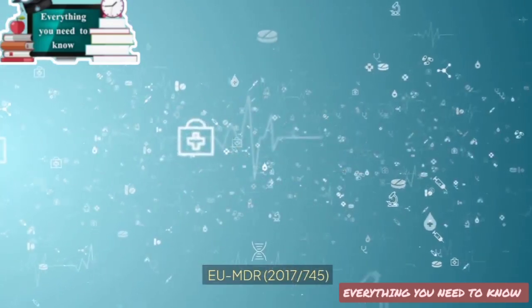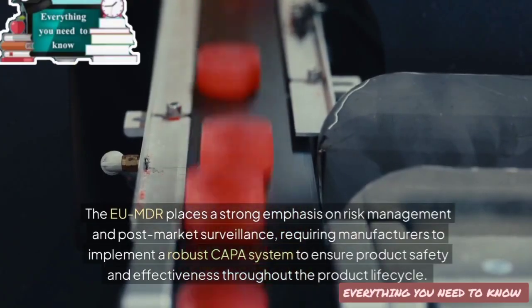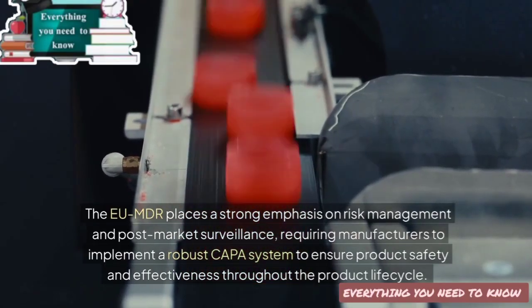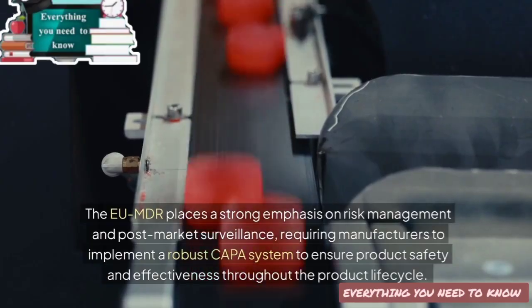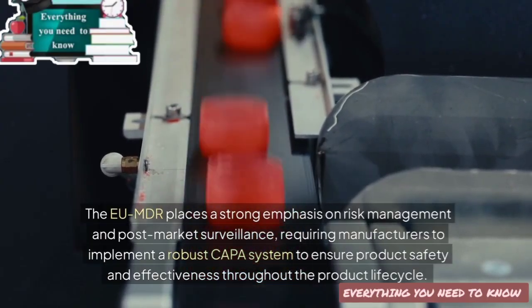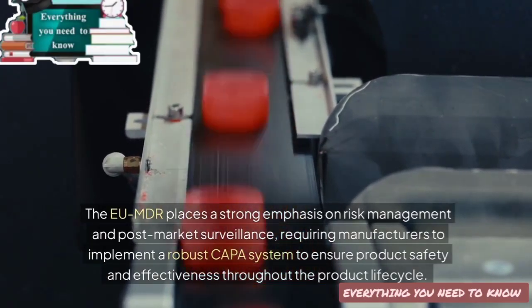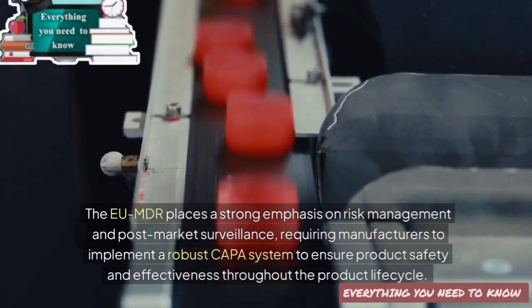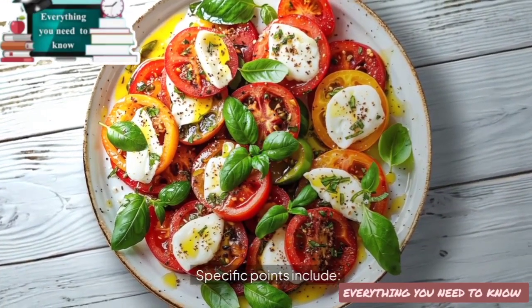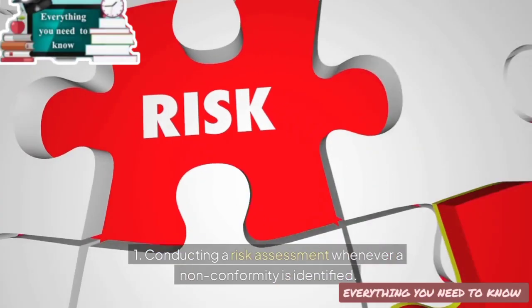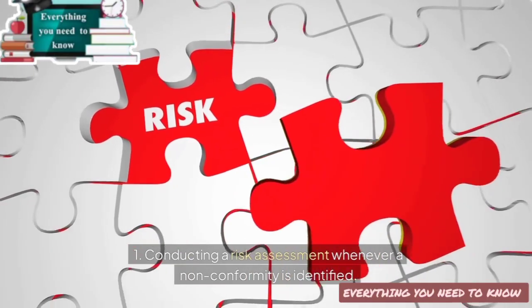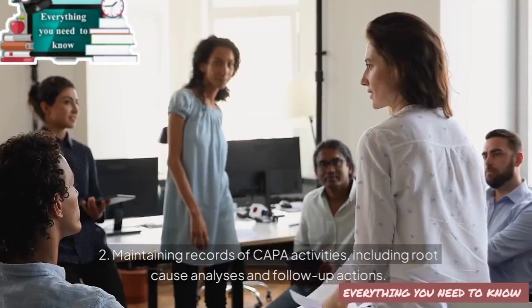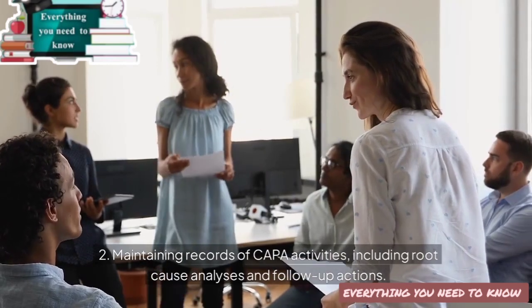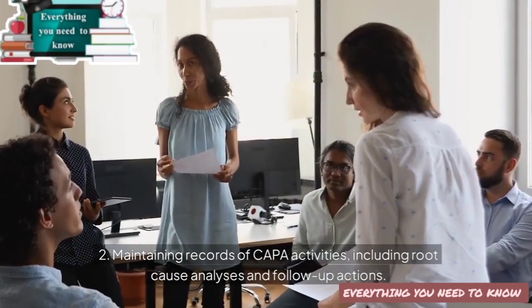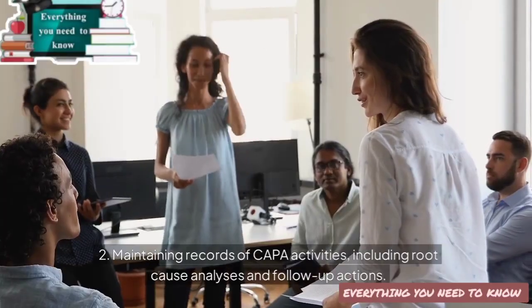EU MDR 2017/745. The EU MDR places a strong emphasis on risk management and post-market surveillance, requiring manufacturers to implement a robust CAPA system to ensure product safety and effectiveness throughout the product lifecycle. Specific points include: 1. Conducting a risk assessment whenever a nonconformity is identified. 2. Maintaining records of CAPA activities, including root cause analyses and follow-up actions.